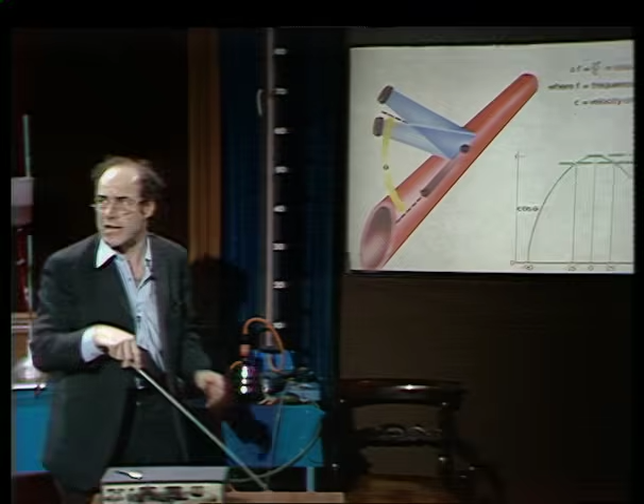For instance, if the beam was absolutely at right angles to the vessel, would we get any change at all or not? Any ideas? No. We got no change at all because there's no component of velocity in the direction of the beam. So clearly, the more nearly we can get parallel with the beam, the bigger the effect will be.